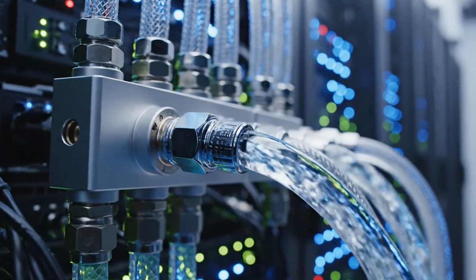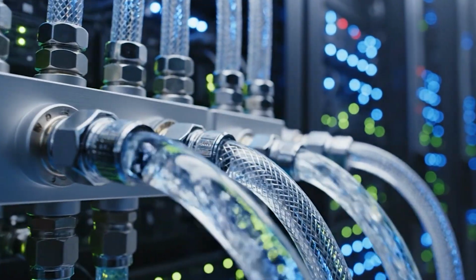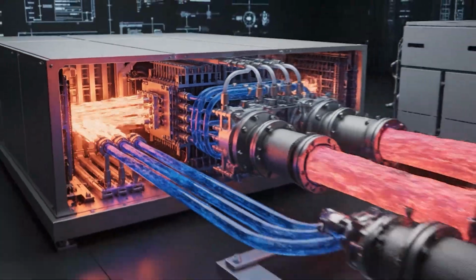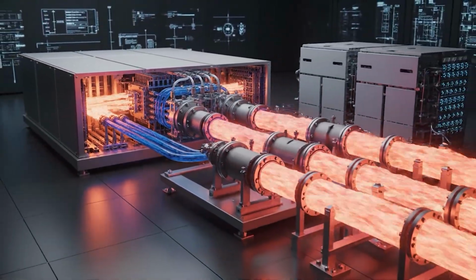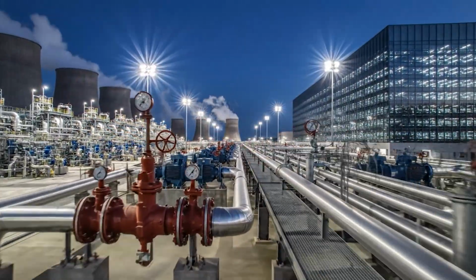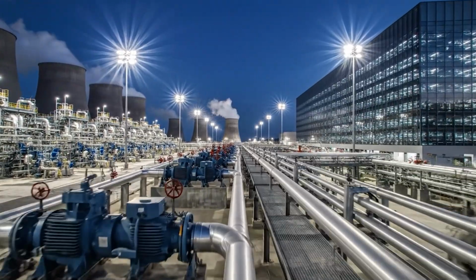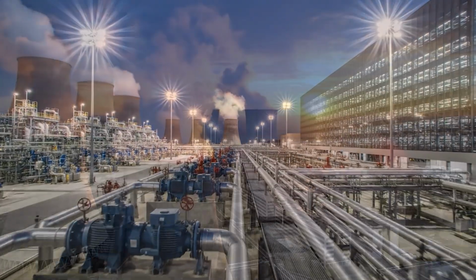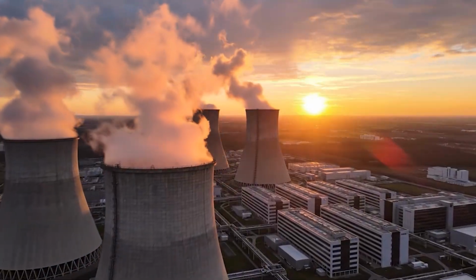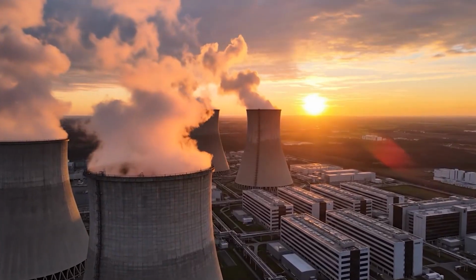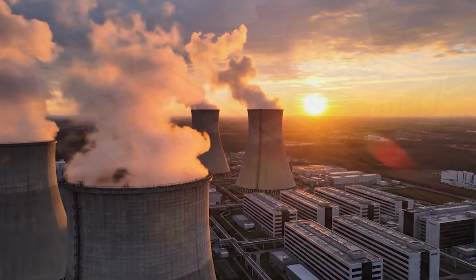In high-density AI rooms, liquid cooling can move heat more efficiently than air. Heat exchangers separate the computing environment from the larger cooling plant. Outside the data halls, chillers and pumps become part of the computation system, and the heat finally leaves the campus through towers, radiators, or other heat rejection systems.